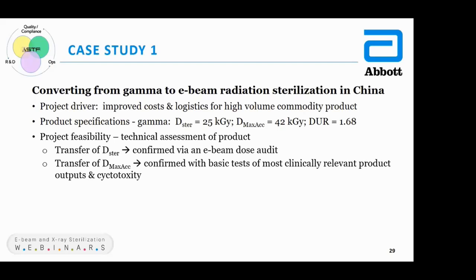So using the same dose establishment that was done with gamma and the same verification dose, a dose audit was done with e-beam, and we got the same results, confirming that with the bioburden under control, we have the same number of organisms, and that the resistance of those organisms to e-beam versus gamma was equivalent. That was experimental data confirming our expectation.